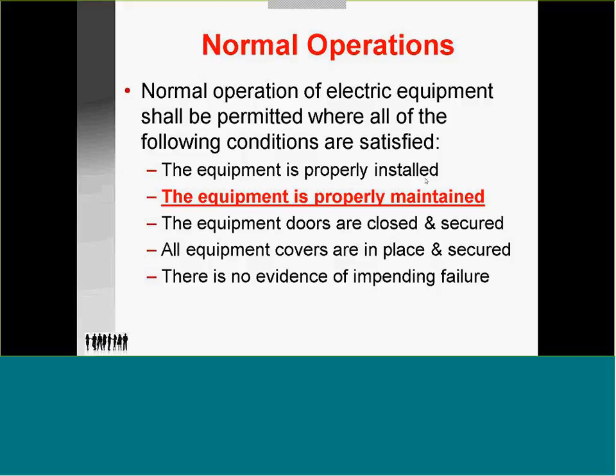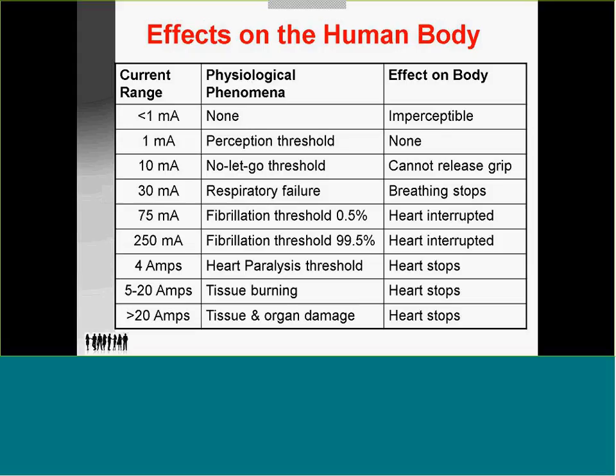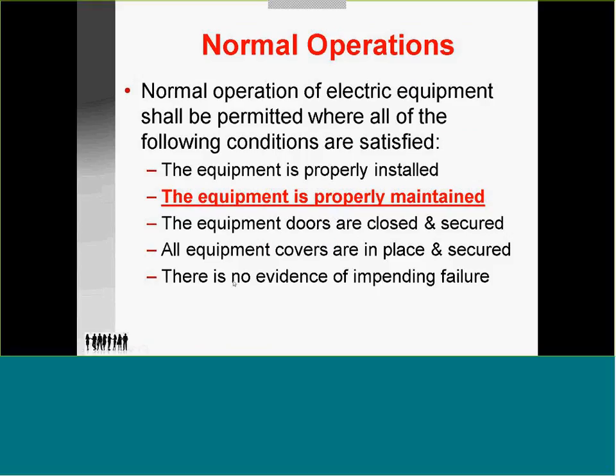An electrician out here in California installed a 4,800 amp line using the 3 conductors and the conduit as the neutral. That has been outlawed for over 20 years now, and he was having trouble with the operation because the ground was not adequate to serve as a neutral. The person had been doing electrical work for over 35 years and had not gone back to any training. So this became an issue. Covers are to be closed and secured.